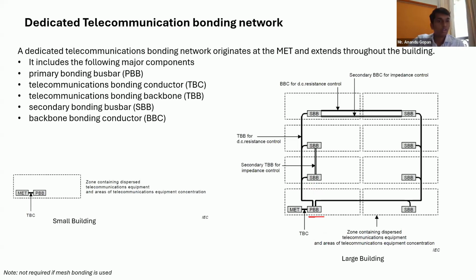If you are going to connect, you have to follow those requirements. This SBB and PBB, what will be connected are your TBC, your TBB, and your RCB. Your RCB is your rack bonding conductors. You have your structural metals. You will have your local SPDs.